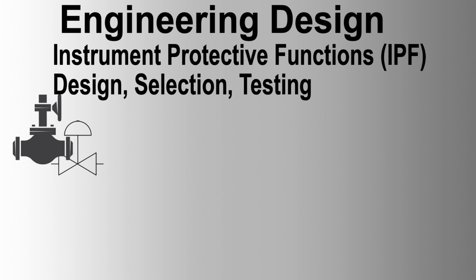To assess the supplier's recommendation for spare parts, theoretical failure rate figures of all boards, power supply units, and other functional subassemblies in the system should be given in the quotation. Calculations should be based on the worst case and the normal environmental conditions specified. The supplier should indicate whether anti-static precautions are necessary when handling cards. If such precautions are required, grounding wrist straps should be supplied as permanently installed items.